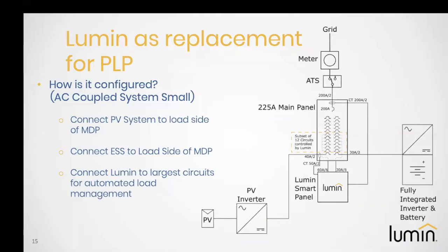So the first example is a relatively small AC coupled solar and storage system. The first thing that you'll notice is that the automatic transfer switch or microgrid interconnect device is located between the meter and the main distribution panel. You can see that right here. Traditionally, we would have seen that ATS, or really an inverter with a built-in transfer capability, positioned further downstream between the main distribution panel and a protected loads panel. Next, you can see in the diagram that both the PV system and the energy storage system are connected through separate load side connections to the main distribution panel. So one here, and then the other being here.